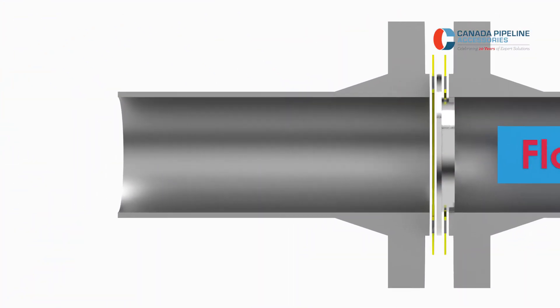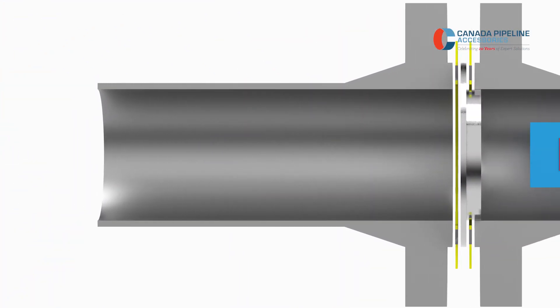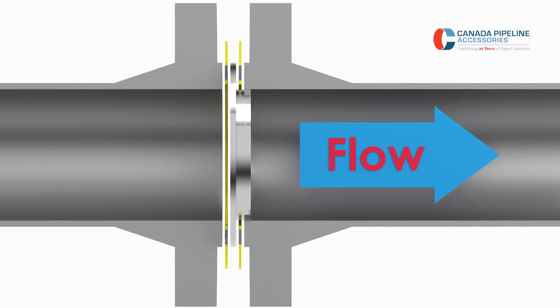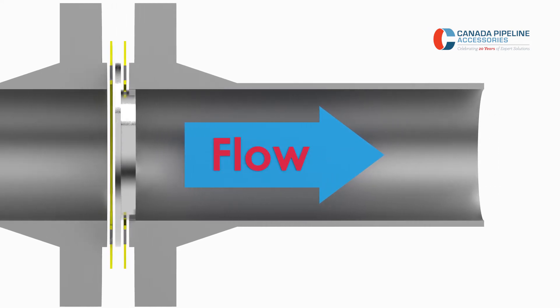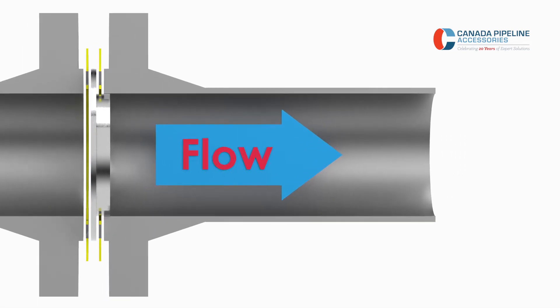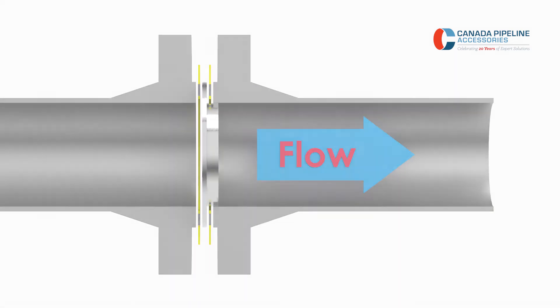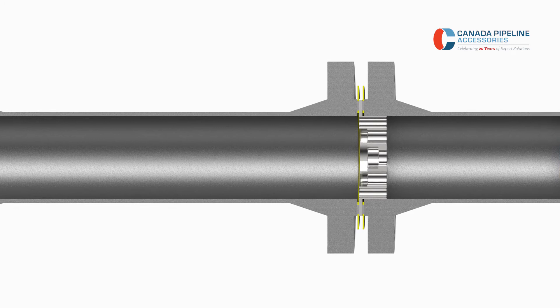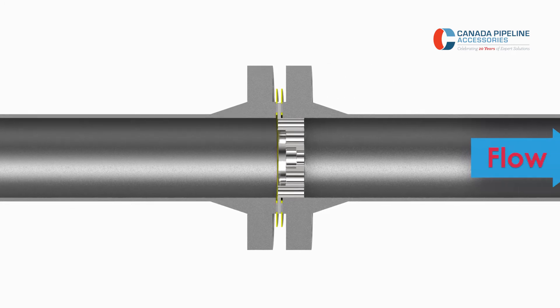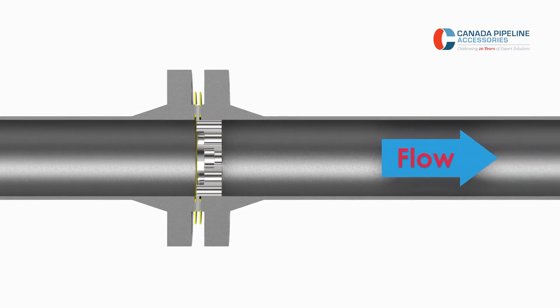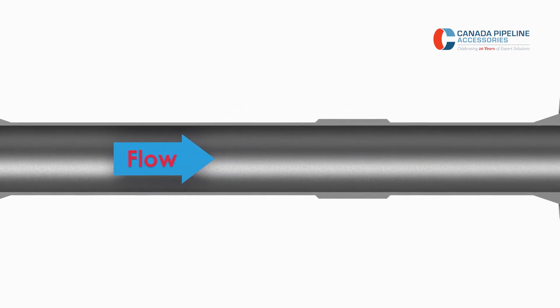CPA type A flow conditioners are installed so the flange end is typically always pointing upstream. The offset portion will install into the pipe that is immediately upstream of the meter. This ensures the flow conditioner is centered relative to the flow meter, maximizing meter performance.